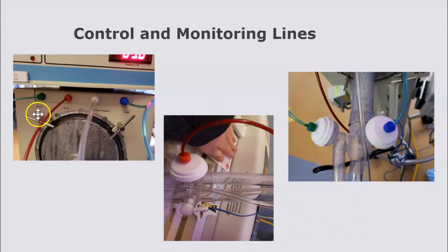If any of them are going to give you trouble, it's this green line. Sometimes a little bit of condensation will get in there, and it'll cause your mean airway pressure to flip-flop everywhere. Just empty that out or replace it if you're having excessive issues. Also, on the other side of this, there are little holes right here on this circuit. That's where you will dump the additional condensation, and some will drip down from the diaphragm.